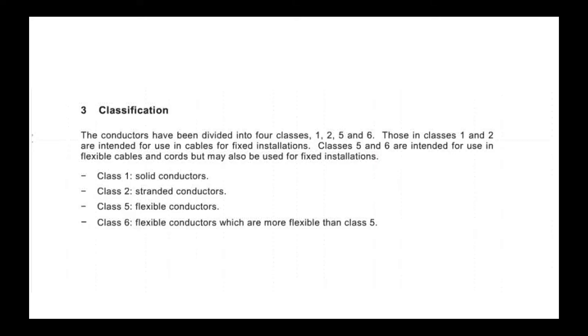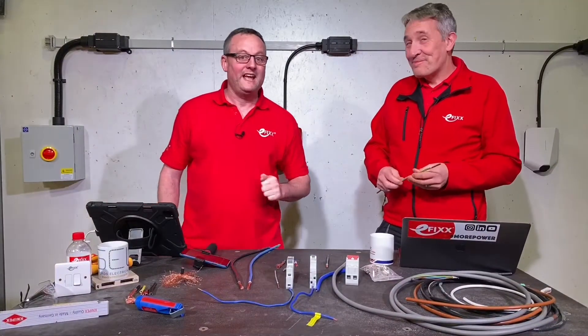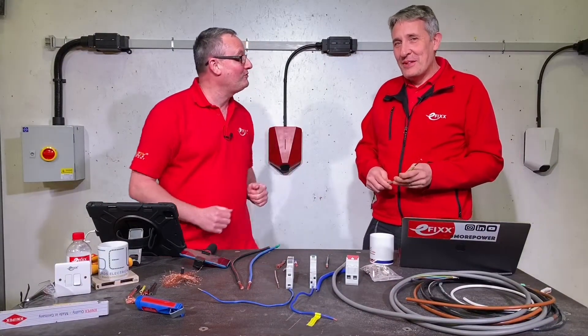Bringing up the slide — class 1 is solid conductors, class 2 is stranded conductors, and both class 1 and class 2 are suitable for use in fixed wiring. Class 5 is a flexible conductor, and class 6 conductors are more flexible than class 5 — just a little bit more flexible, which makes logical sense.